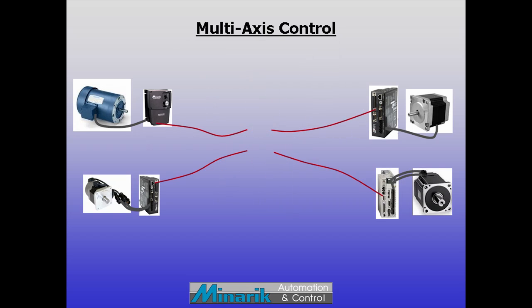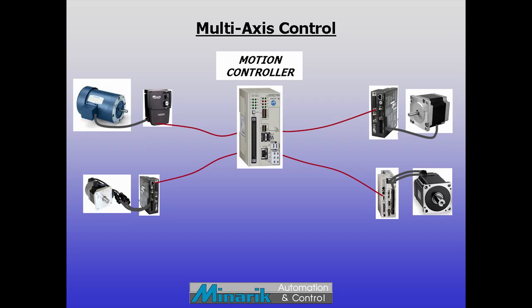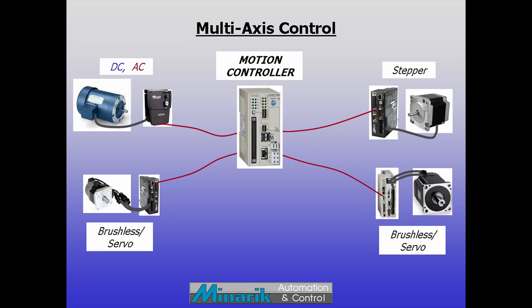However, when motion requirements become intensive, the next choice for designers are known as dedicated motion controllers. Motion controllers are specifically designed for use with motor drives. Most can control any technology, but they're usually paired with steppers or servos. Depending on the product, they can control from two, to several, up to hundreds of axes of simultaneous and coordinated motion.